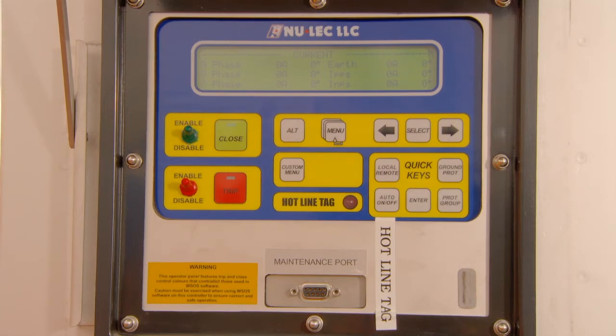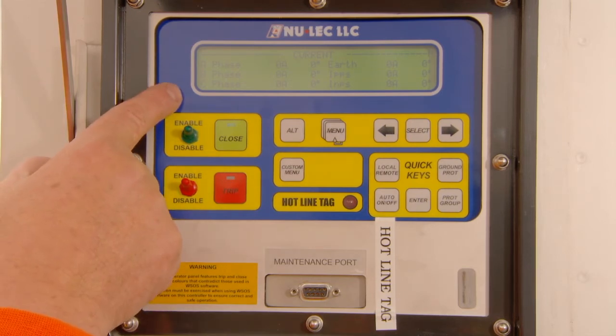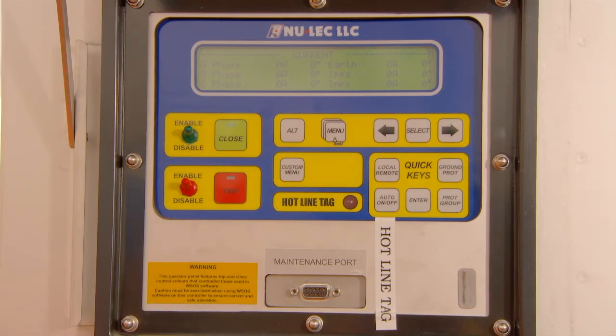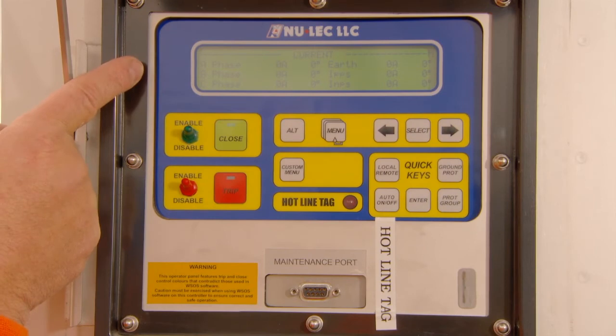If you reclose the unit with the bypass switch still closed, a percentage of current will go through the recloser and a percentage through the bypass switch. When you open the bypass switch, then each phase will be taking the full current through the recloser, and the amperages on the display will change accordingly. You will then know how much current is flowing through the unit.